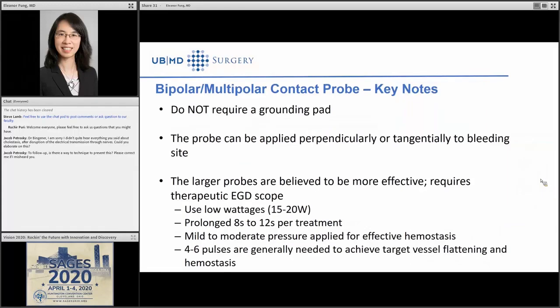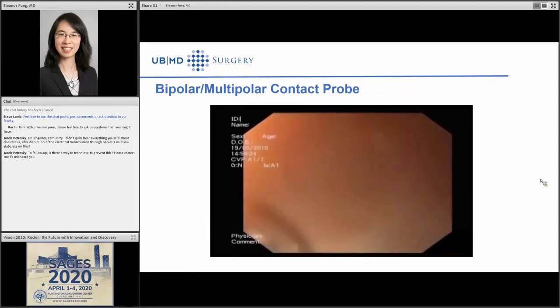In terms of the key notes, you don't need a grounding pad because this is a bipolar device, and you don't have to be extremely accurate in how you do it. You can either do it perpendicularly or tangentially. Larger probes are generally found to be more effective, so a larger therapeutic gastroscope is helpful. You want to generally use 15 to 20 watts of voltage and apply mild to moderate pressure, with 4 to 6 pulses to achieve target vessel flattening and hemostasis. So we're going to go into a video of how this is used. I might fast forward some of it.